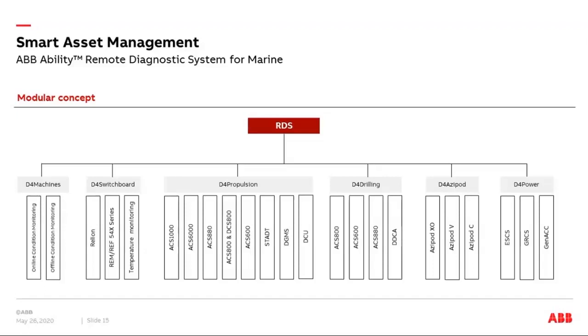In addition to that, we have a temperature monitoring system that replaces the need or requirement for IR temperature or thermographic imaging of switchboards. Instead, it's an online system where the RDS system is continuously collecting temperature information from various hotspots, busbar connections, cable connections, tulip connections, and so on in the breaker system.